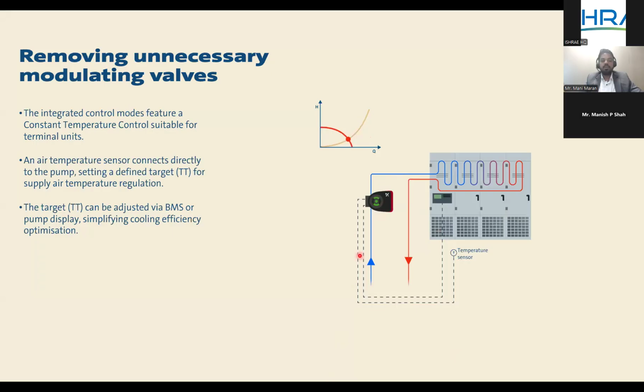And that's where we say the system is a temperature dependent system, whereas the conventional valve-based system is a pressure dependent system. Modulating the flow based on temperature is more accurate, faster, and energy efficient, and that's where we get savings on the operation side of it.